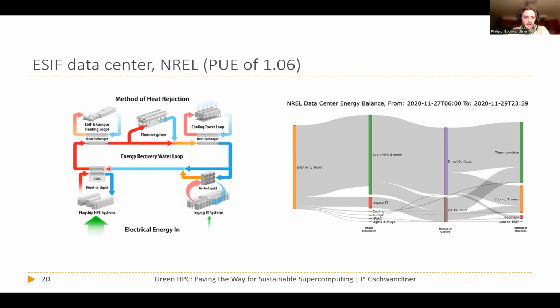You get cold water into your flagship HPC system, which has the highest power draw and is the largest heat dissipator. Then hot water comes out of the system, and through a heat exchanger, you actually heat the office building and the campus with it. That's something every larger system has to do these days, otherwise you cannot operate efficiently or sustainably anymore, because nobody wants to simply dissipate heat out on the roof when office buildings next door need heating for people to work comfortably when it's minus 10 degrees outside.